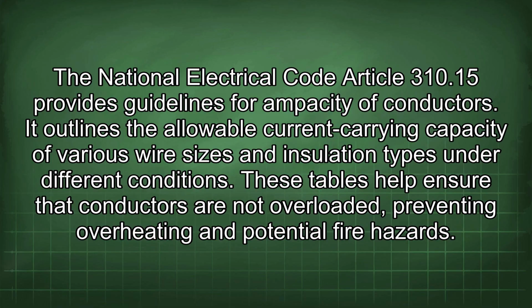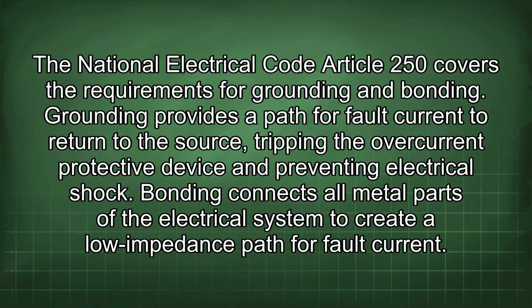It outlines the allowable current carrying capacity of various wire sizes and insulation types under different conditions. These tables help ensure that conductors are not overloaded, preventing overheating and potential fire hazards. The National Electrical Code Article 250 covers the requirements for grounding and bonding. Grounding provides a path for fault current to return to the source, tripping the overcurrent protective device and preventing electrical shock. Bonding connects all metal parts of the electrical system to create a low impedance path for fault current.